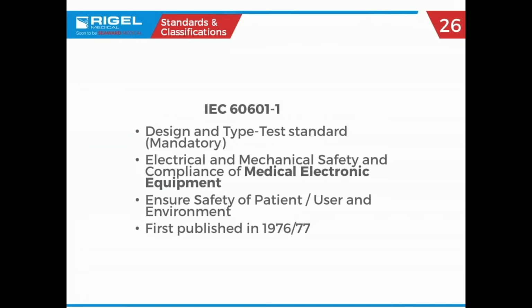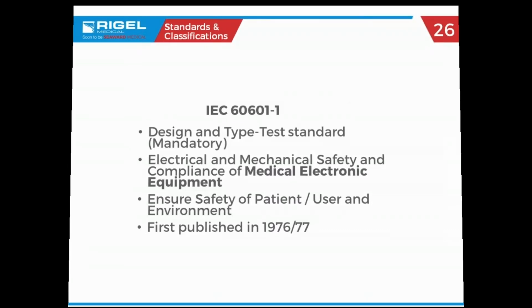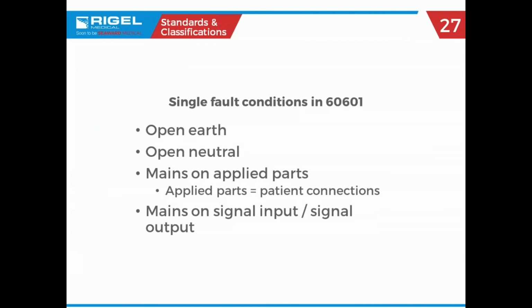So IEC 60601-1. Again, this is the qualification standard that every medical device during its design and manufacture has to be tested to. Period. First published in '76, and again, why we're doing all of this is for operator safety and patient safety. So in all of these tests, we start to talk about single fault conditions. Single fault condition is something went wrong.